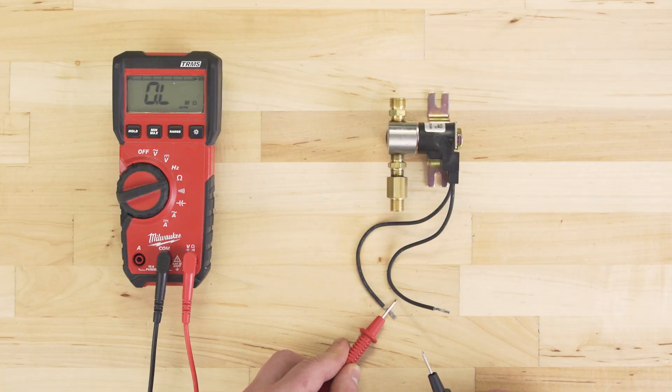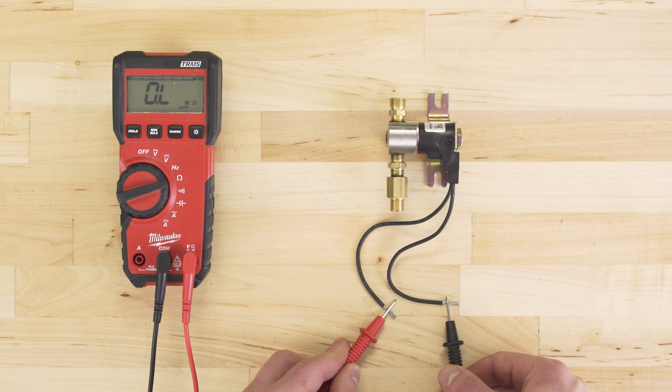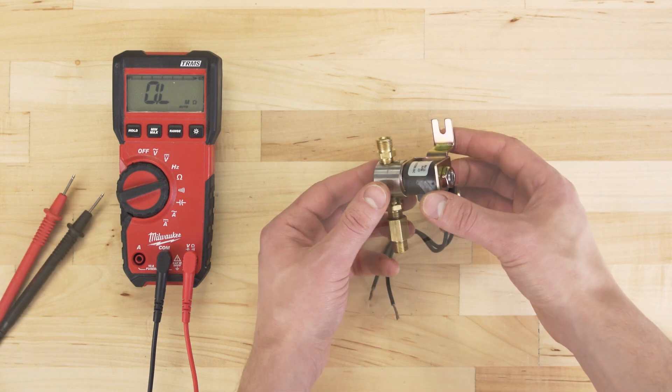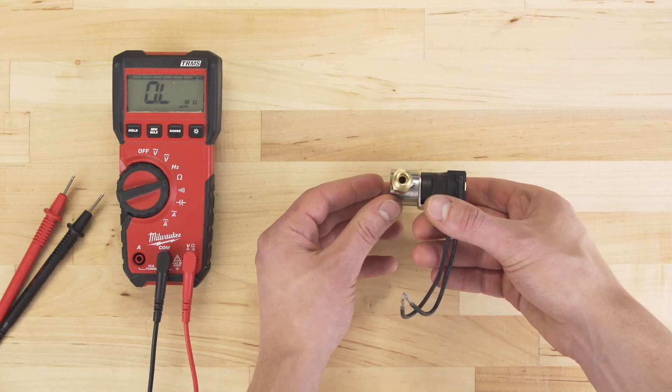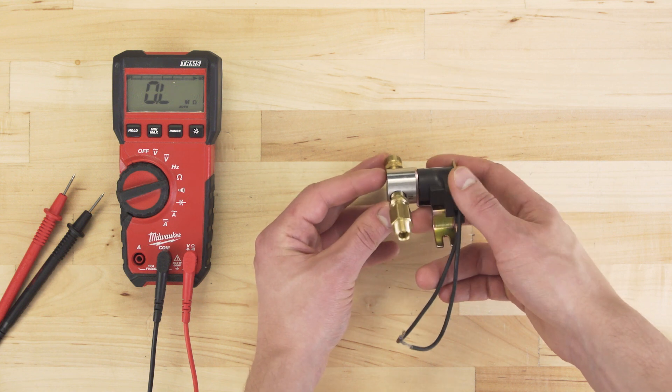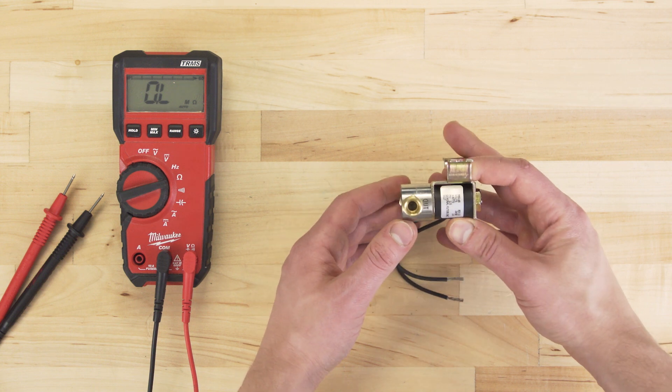Now if the solenoid doesn't have continuity, then the coil will not energize, and the valve will not open. Keep in mind, solenoids can also fail mechanically, and even with continuity, the valve might be stuck open or stuck closed.